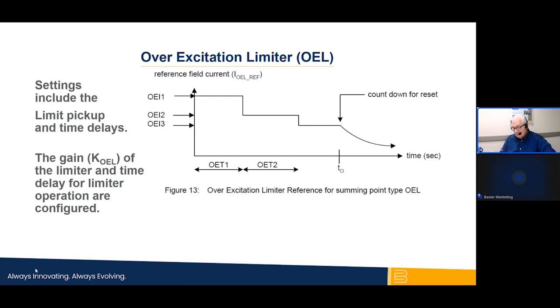There are numerous variations on the design of OEL and OEP devices, but they all operate upon the same principles. Monitor the machine excitation level, allowing it to be raised above the determined level of the continuous field current for a short period of time, and reduce or remove excitation after that time is exceeded. The limiting action allows a machine to support a stressed bulk electrical system as much as is practical without incurring thermal damage to the field winding.